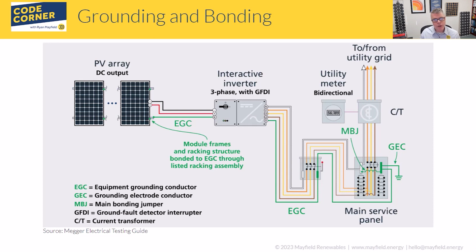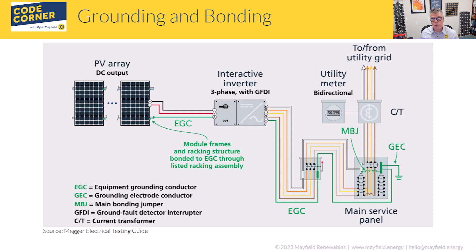The equipment grounding conductor connects the PV array back to the inverter. In modern systems using non-isolated or transformerless inverters, the EGC actually continues out of the inverter on the AC side, through the disconnect, all the way to the point of interconnection. In this grid-direct example with no storage, the EGC runs from the PV array all the way to the main service panel where it's bonded to the grounding system.